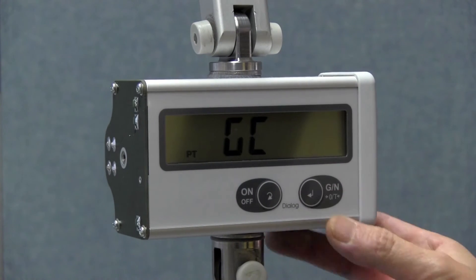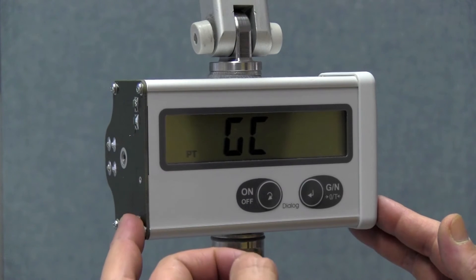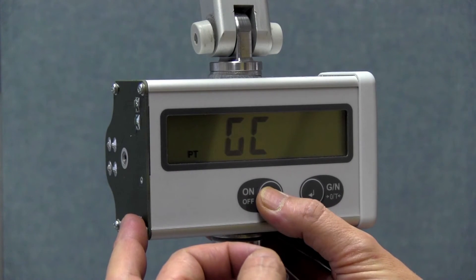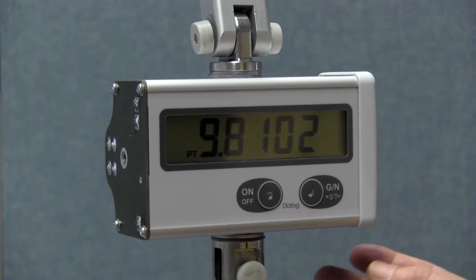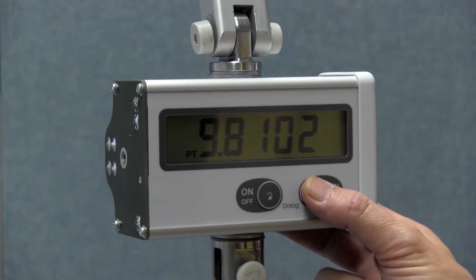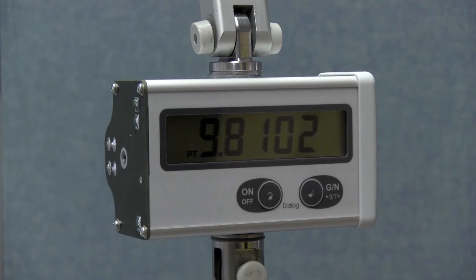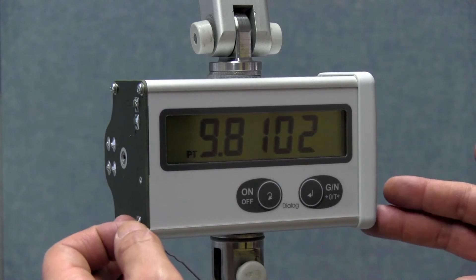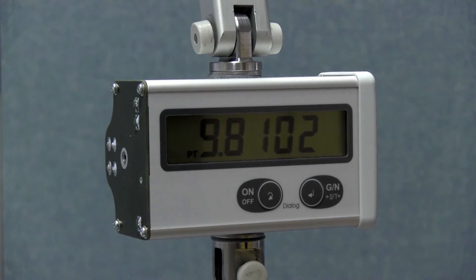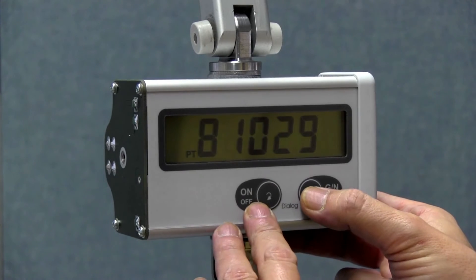The gravitational acceleration factor, GC, which acts on the scale during calibration with weights, can be displayed or changed. Currently the display shows 9.81029, which is the G factor in Darmstadt, Germany. I can either confirm or overwrite this factor. To confirm it, I have to press the on-off key again so that the leading 9.0 disappears. Then I confirm the value.